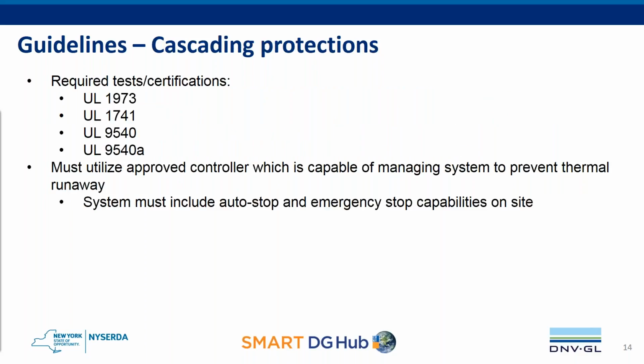For cascading protections, as I mentioned, this is where the standard heavy items are. So there are required testing and certification. So UL 1973, 1741, and 9540 have all been noted earlier. UL 9540A is a relatively new test protocol, and it is being looked for all systems being installed.